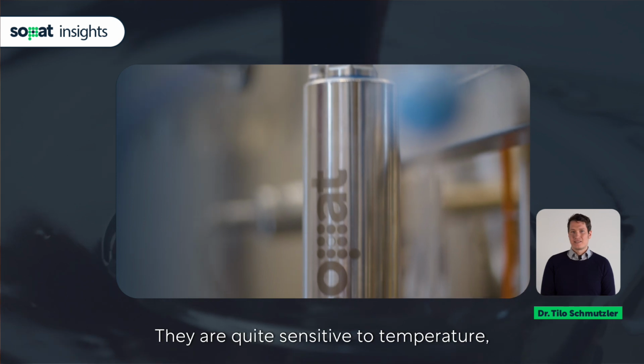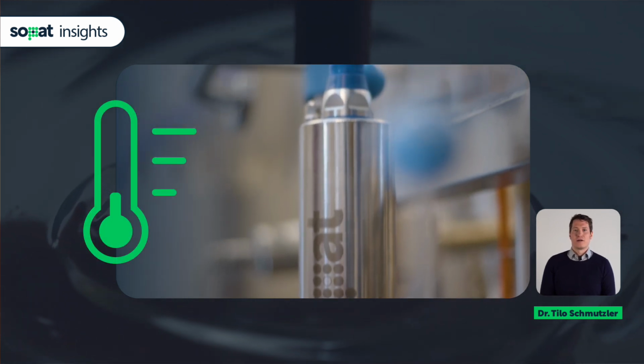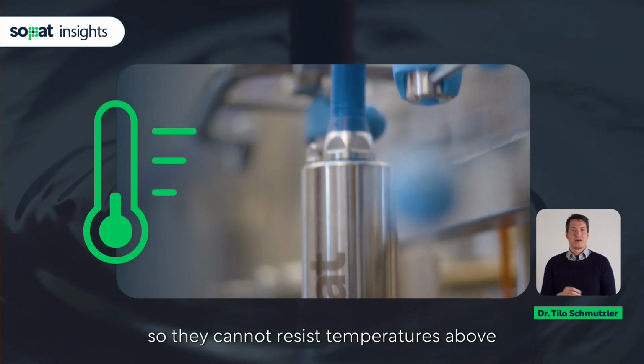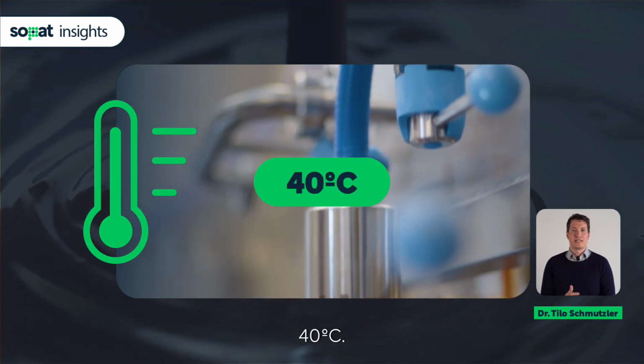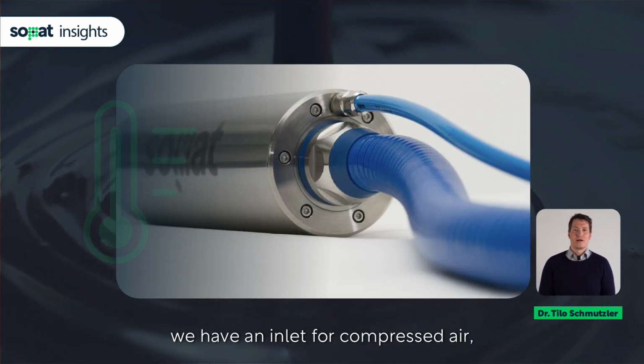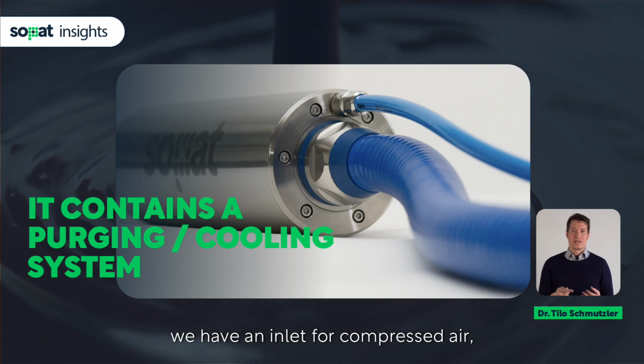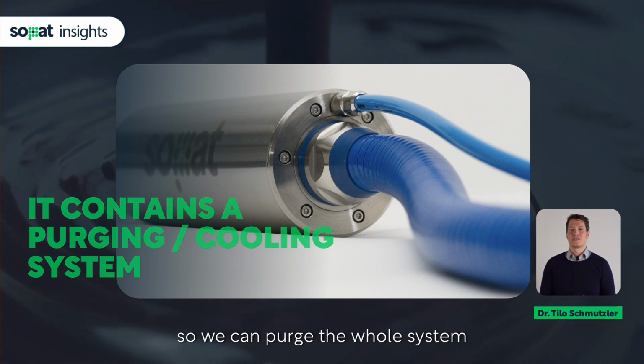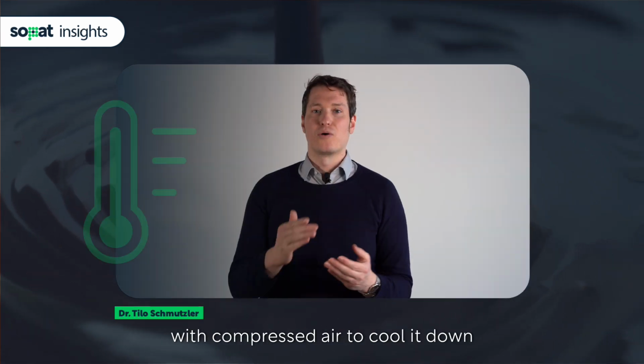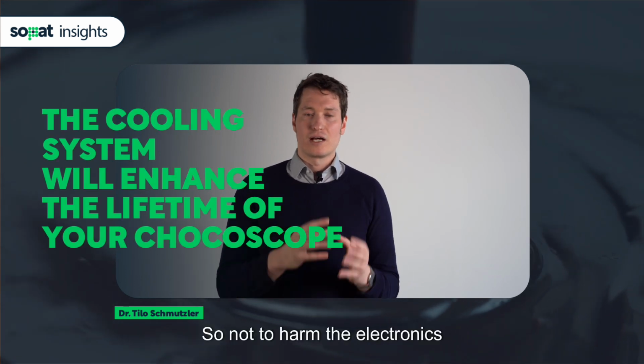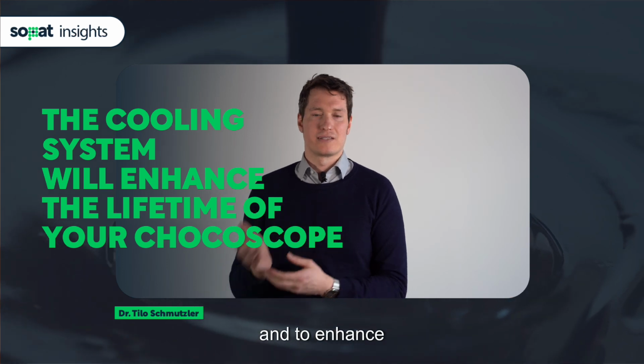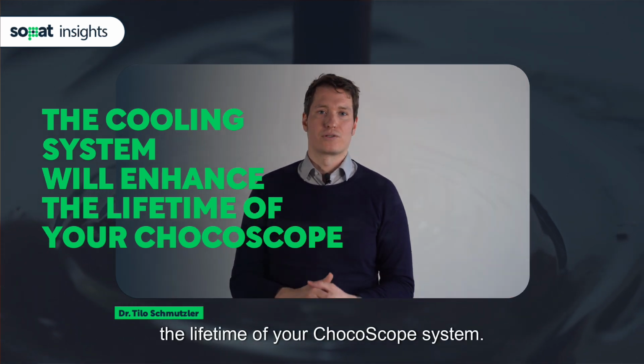They are quite sensitive to temperature, so they cannot resist temperatures above 40 degrees centigrade. So at the end of the probe we have an inlet for compressed air, so we can purge the whole system with compressed air to cool it down to 40 degrees centigrade. So as not to harm the electronics and to enhance the lifetime of your ChocoScope system.